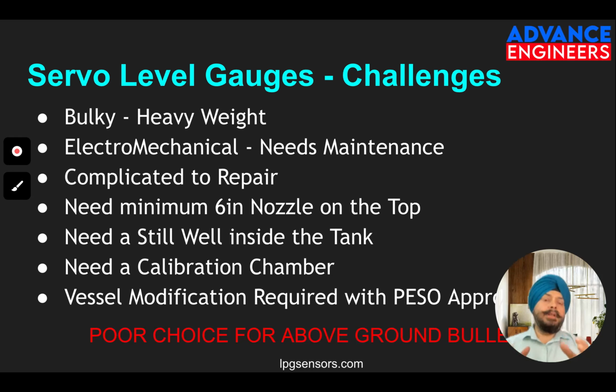So if we are maintaining our servo gauges on a regular basis, they are the perfect gauges. But the challenge here is you need to have a dedicated team to maintain it. You need to have regular spares replacement. You need to have regular calibration being done. You need to check the floats, because the floats also get punctured because of pressure or something. Because the float is a very light float because of the LPG density. You need to have a very light float. So all those things. It's a maintenance-prone activity which you need to be very careful about.